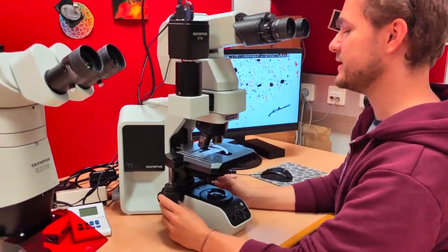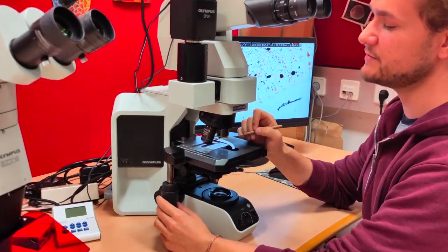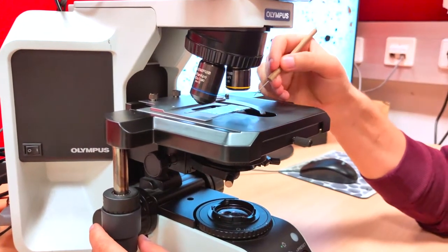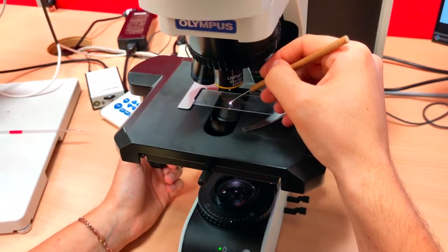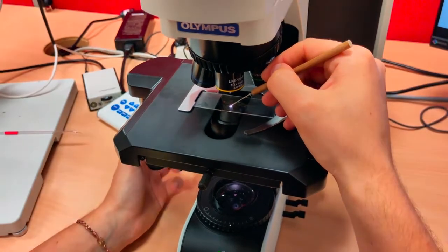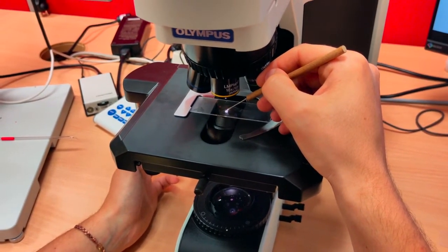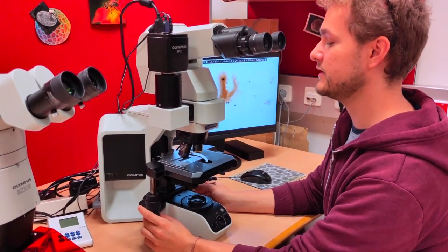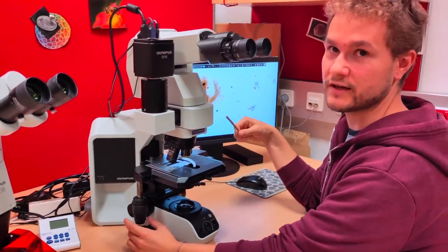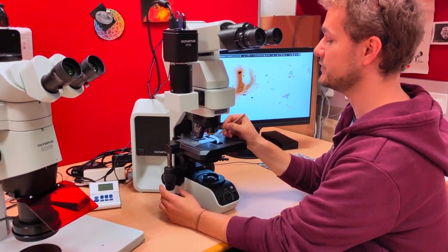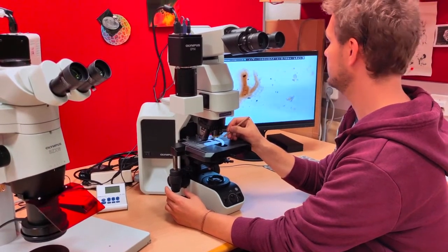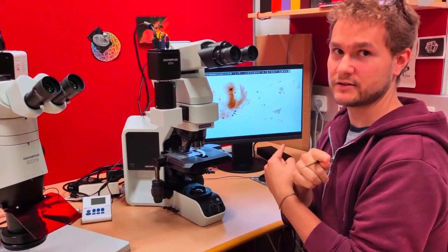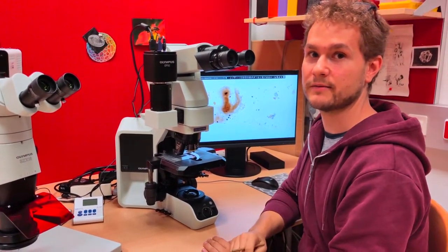So this microscope is special because there's a large distance between the objective and the microscope slide, which allows me to insert this micromanipulator between the object and the lens, and I can manipulate the pollen grains around. It's also a direct image microscope, which means if I move the table left, the image also moves left. So you can see if I insert my hair here, it will be seen also from the right side. Traditional microscopes invert the image and it's very difficult to manipulate it again.